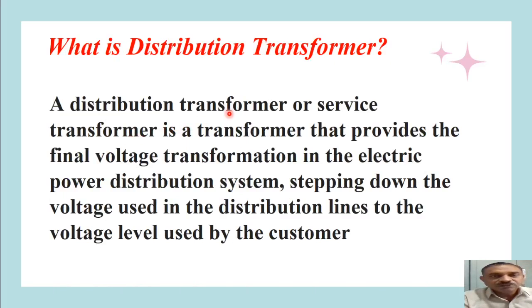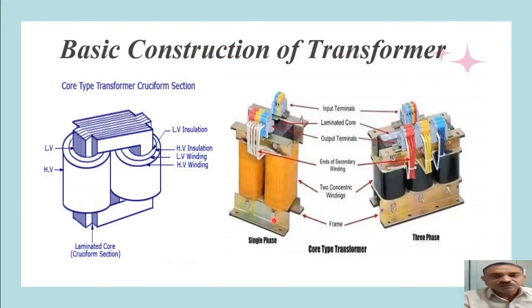Before we study the construction, let us first know what is a distribution transformer. A distribution transformer, or service transformer, is a transformer that provides the final voltage transformation in the electrical power distribution system, stepping down the voltage from distribution lines to the voltage used by consumers. In India, the voltage levels for primary distribution is 11 KV and for secondary or LV distribution it is 415 volts.